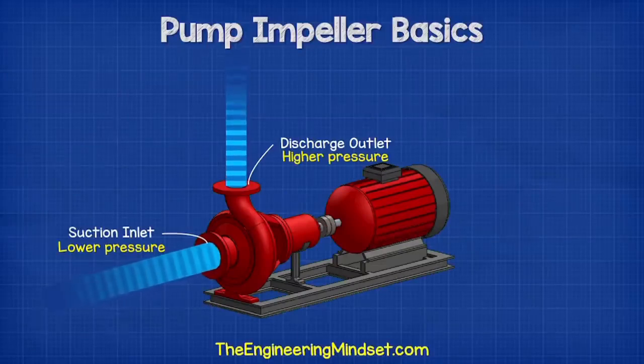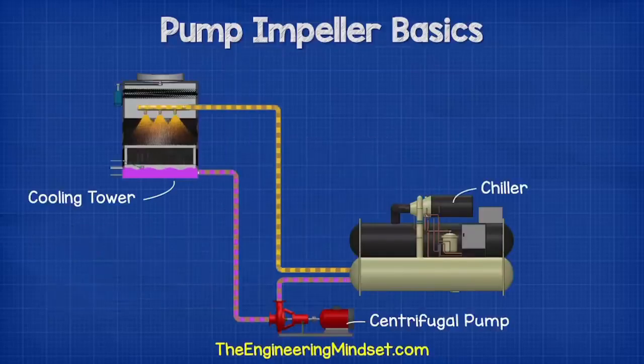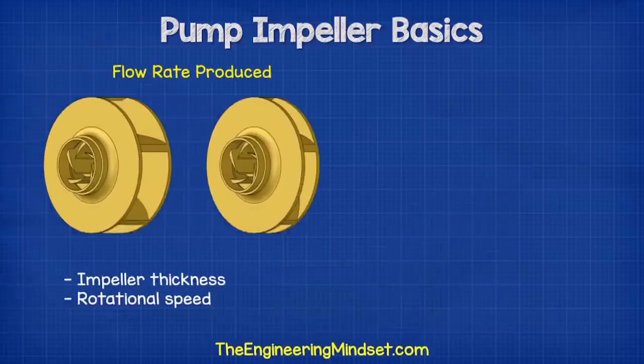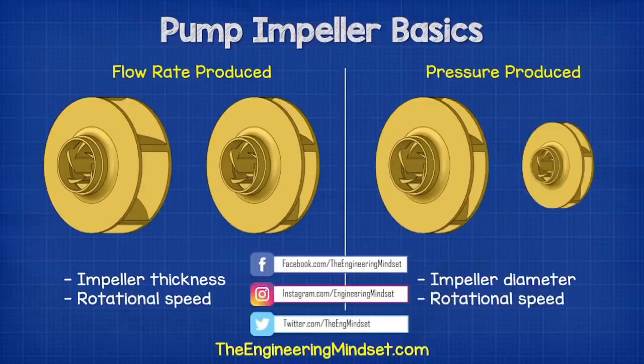The high pressure at the discharge allows us to force the fluid through pipes and into a storage tank or around a pipe system. The thickness of the impeller and the rotational speed affects the volume flow rate from the pump, but the diameter of the impeller and the rotational speed will increase the pressure it can produce.